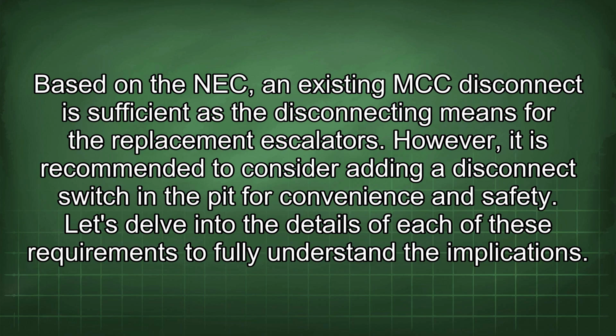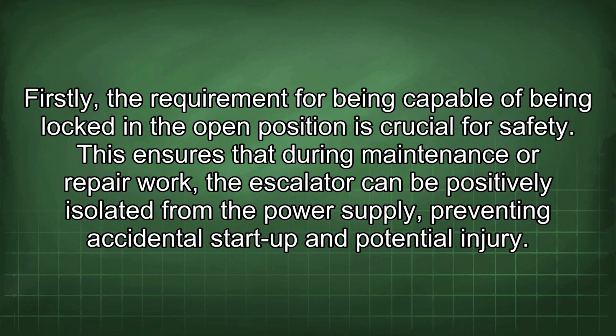Based on the NEC, an existing MCC disconnect is sufficient as the disconnecting means for the replacement escalators. However, it is recommended to consider adding a disconnect switch in the pit for convenience and safety. Let's delve into the details of each of these requirements to fully understand the implications. Firstly, the requirement for being capable of being locked in the open position is crucial for safety.